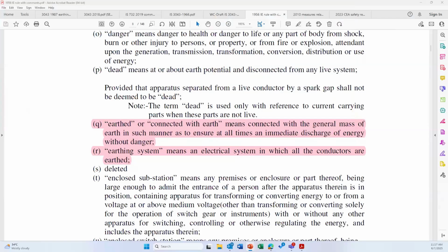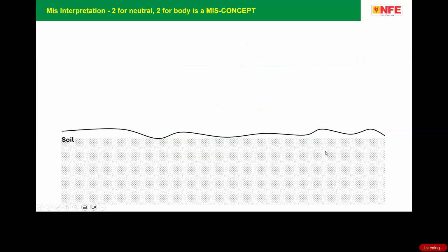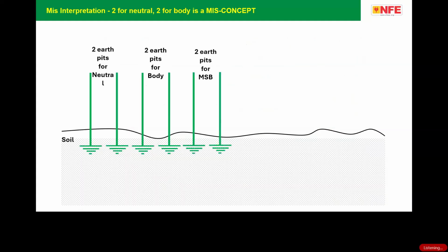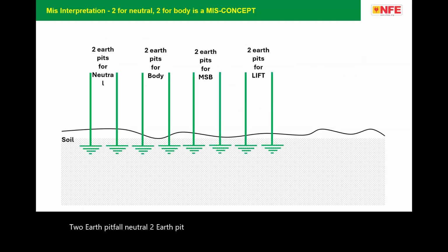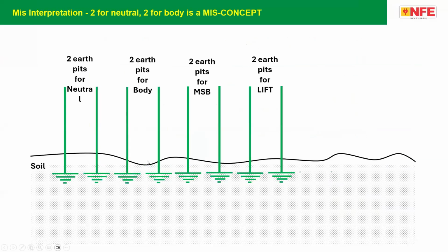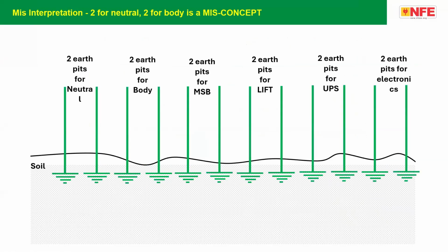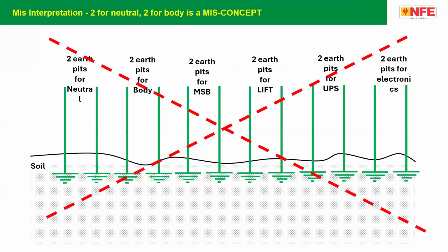Practically, what has happened because of these mistakes or misinterpretations in the definition? We have the habit of connecting two earth pits for neutral, two earth pits for body, two earth pits for the main distribution board, two earth pits for lift, two earth pits for UPS, one or two earth pits for electronics, and everywhere, all around the building, we started putting earth electrodes.